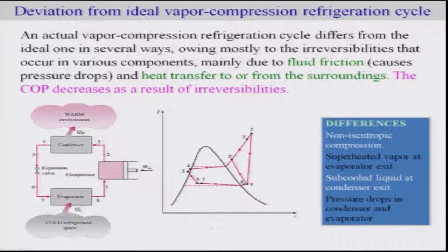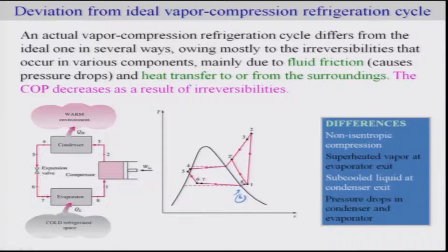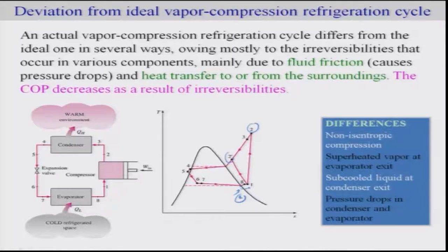In reality, there will be deviations from the ideal vapor compression refrigeration cycle, mainly due to fluid friction across the pipes and heat transfer from or to the surroundings. In the practical or real scenario, there may be pressure losses, so it is more useful to have the refrigerant slightly superheated before it enters the compressor. At the compressor, friction would increase entropy, while heat transfer can increase or decrease entropy depending on its direction. The exit state can end at point 2 or 2' depending on which effect dominates.